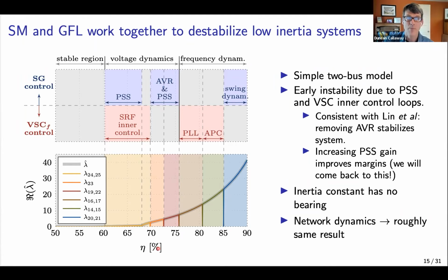At 60% penetration, meaning 40% of our generation is left coming from synchronous machines, with the remaining 60% coming from grid-following converters, the real part of that largest eigenvalue crosses over into the right half plane and we have an instability show up. That real part gets larger and larger as we add more generation from grid-following converters. This is consistent with some results we've seen before, in particular the Lin et al. paper I mentioned, observing similar instabilities. This is focusing on what we call algebraic network models.